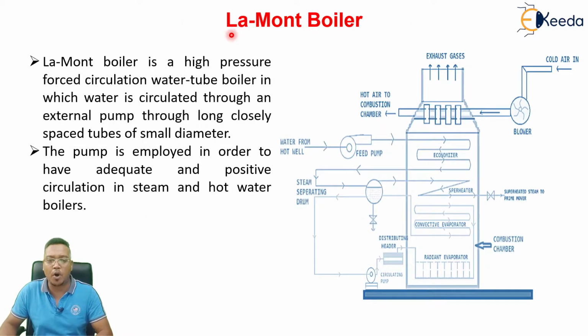First, the Lamont boiler. The Lamont boiler is a high pressure forced circulation water tube boiler in which water is circulated through an external pump through long closely spaced tubes of small diameter. The pump is employed in order to have adequate and positive circulation of steam and hot water. We are using this pump, because of that the Lamont boiler is a forced circulation system.